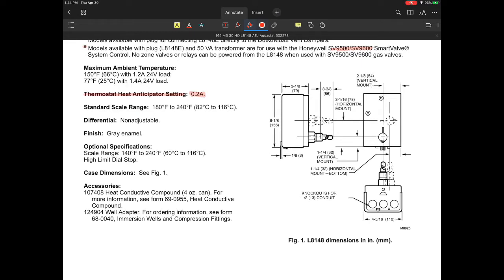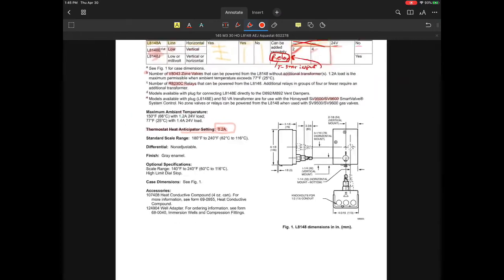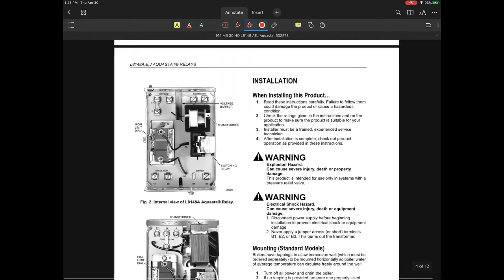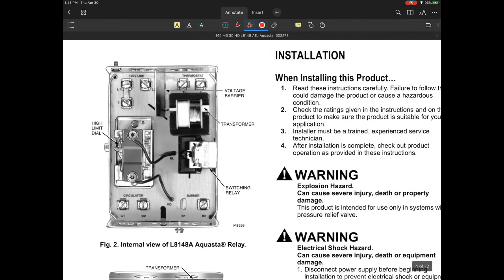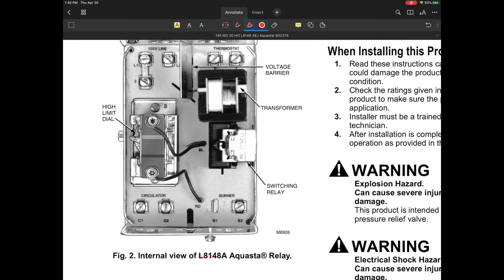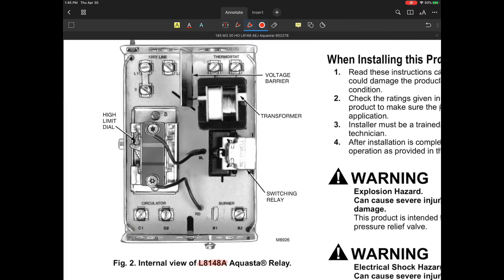All the other things we hit on there. Now, they talk about a thermostat anticipator setting of 0.2 amps. Unless you are using one boiler, one pump, circulating through all the zones at the same time, and you don't really have any individual zones, and you have a thermostat that's so basic that it has the anticipator, they're telling you approximately what the anticipator should be set at. It's very low. Again, most of the time with electronic thermostats we're not really doing that, but they do tell you what the scoop is on that. So, all right.